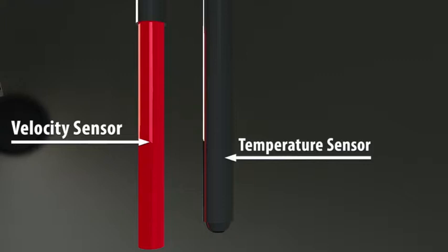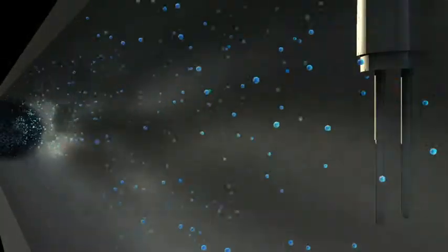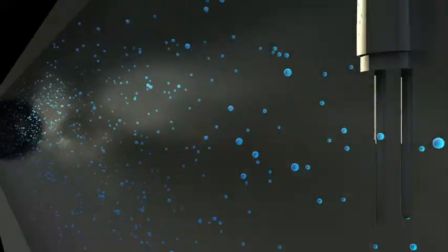As the name implies, thermal dispersion mass flow meters use heat to measure flow. The velocity sensor is heated continuously via electrical wattage so that a predefined temperature differential is always maintained between the two sensors. For example, 50 degrees Celsius is the constant temperature differential for Sierra meters. As soon as the fluid flow begins, heat is drawn from the heated velocity sensor via the gas molecules flowing past. The heat is dispersed as it is carried off by the flow.